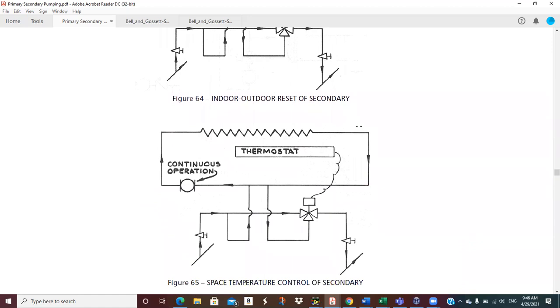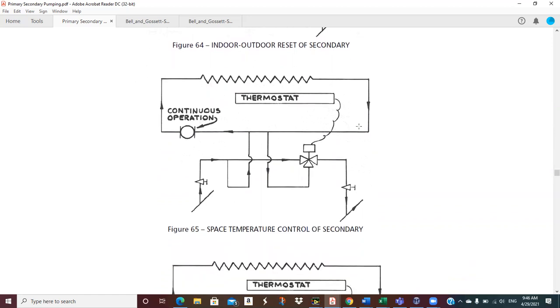We could also do that same thing. Well, we could do reset, or this could be just a simple thermostat setting, and we're going to bleed primary water into the secondary in order to keep the thermostat in the space within its control range, probably plus or minus a degree or a degree and a half, something like that. Keep everybody comfy. So we could do that.